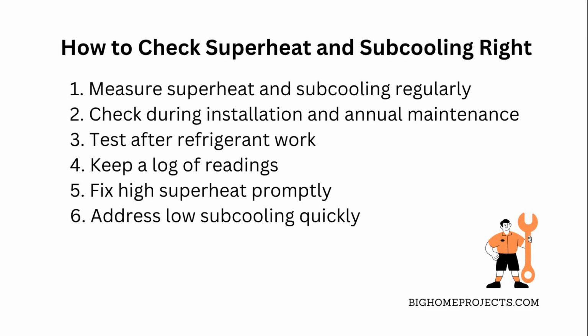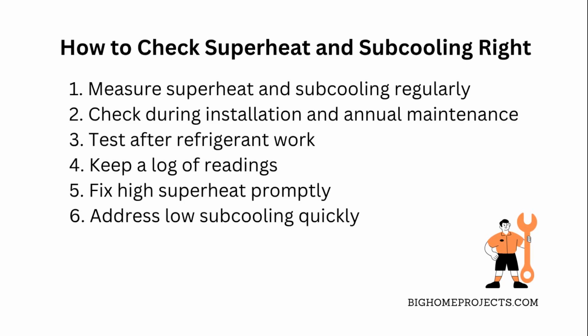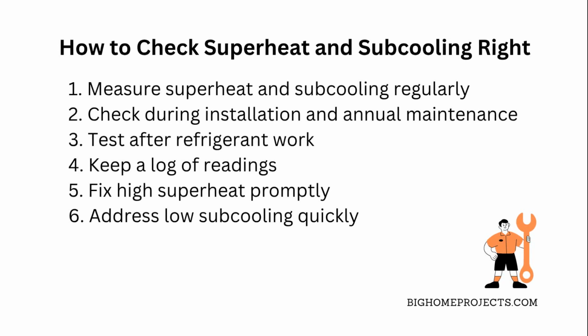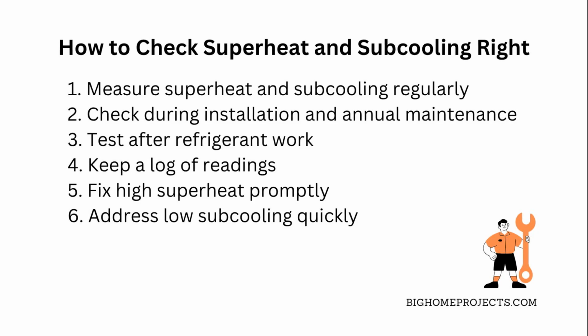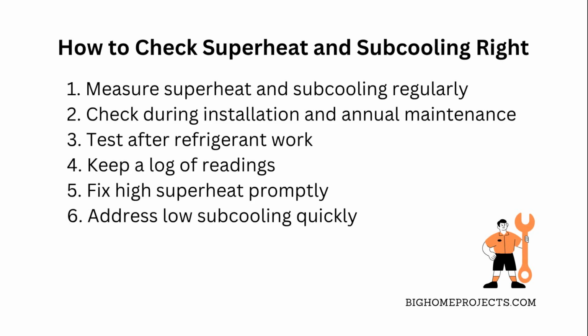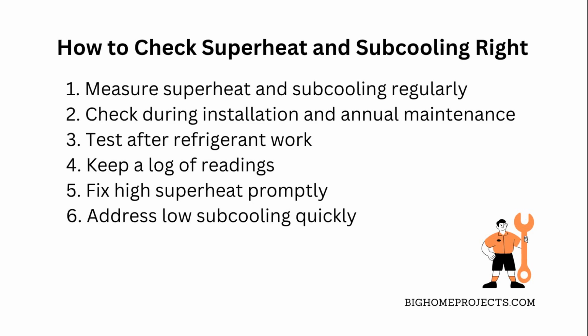To keep things in check, you want to measure these during system commissioning when the unit is first installed, then at least once a year during routine maintenance. Also, anytime a technician adds or removes refrigerant, they should check these levels to avoid overcharging or undercharging the system. Keep a log of these readings so you can spot trends or issues before they become big problems.